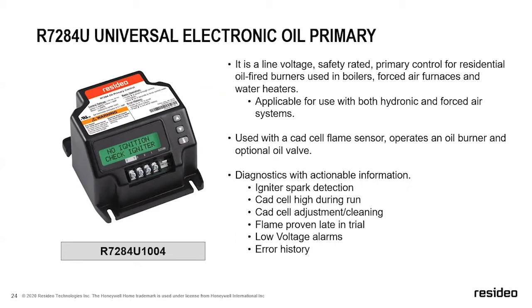Furthermore, it tells you diagnostics with actionable information. So again, plain language, it'll tell you igniter spark detection, whether your CAD cell's resistance is high during the run, or if it needs adjustment and/or cleaning, flame proven late in trial, low voltage alarms, and it also provides an error history. That's really nice for those nuisance calls where maybe they had a power spike or brief momentary power outage. It will let you know that documentation. If you get there and everything's running fine, but the customer was left without heat at a certain time, you can go back in the error log and see what exactly caused that.